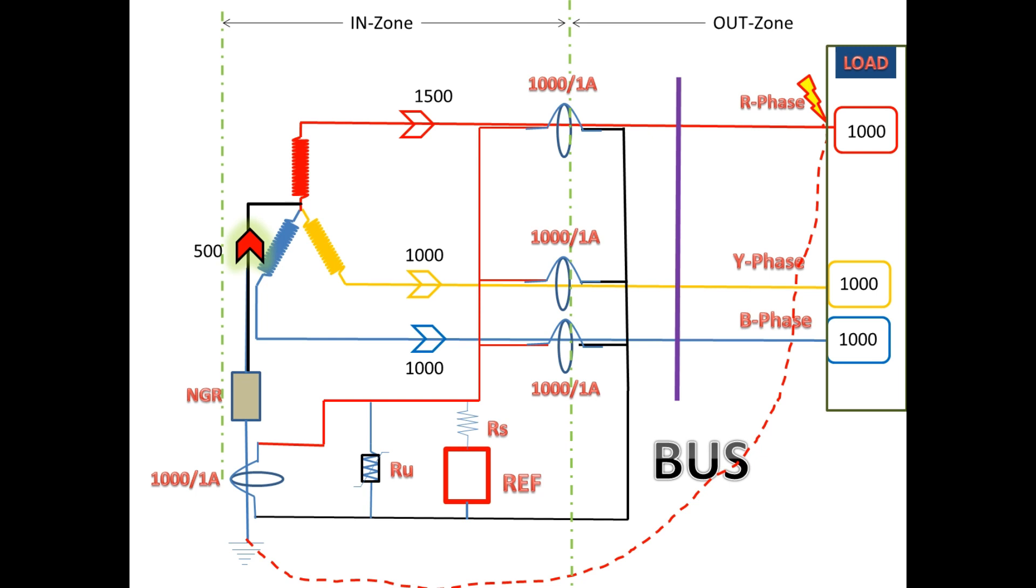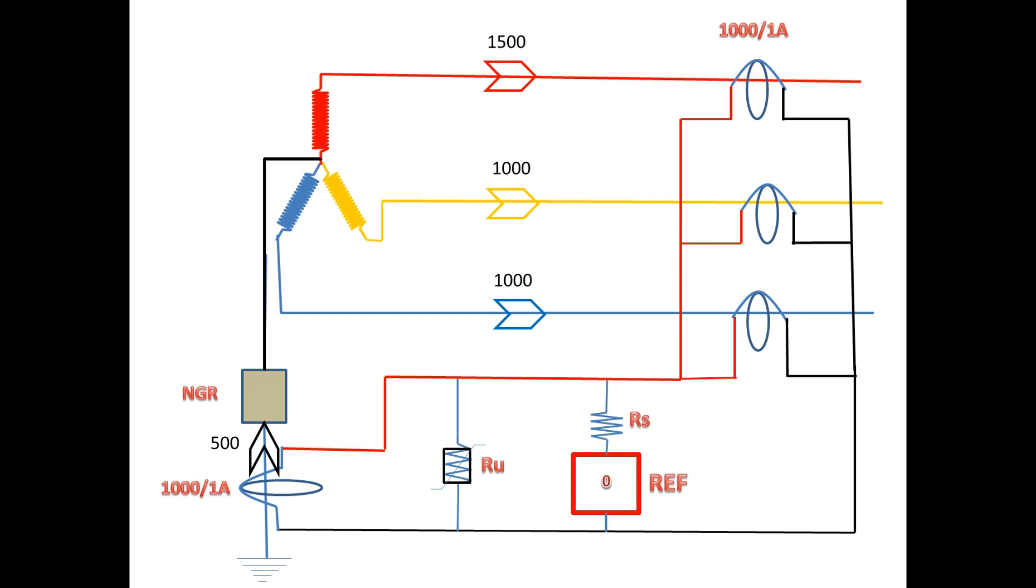R phase will take 1500 amps while the remaining phases will take 1000 amps each. Since it is an earth fault, the current path goes towards the neutral earthing point, so the neutral CT also gets 500 amps. Now for the secondary current: on the core balance CT, according to the CT ratio, R phase secondary current is 1.5 amps and the other two phases get 1 amp each.